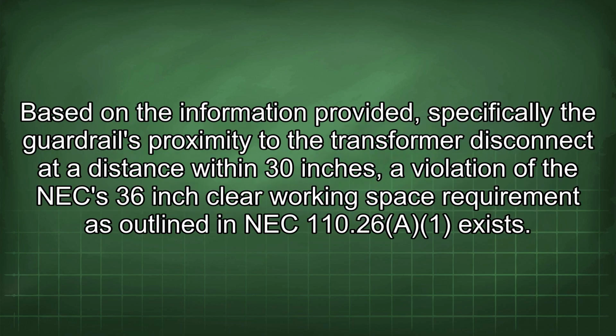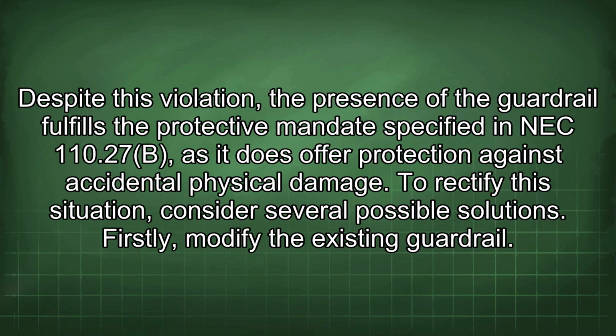Based on the information provided, specifically the guardrail's proximity to the transformer disconnect at a distance within 30 inches, a violation of the NEC 36-inch clear working space requirement as outlined in NEC 110.26(A)(1) exists. Despite this violation, the presence of the guardrail fulfills the protective mandate specified in NEC 110.27(B), as it does offer protection against accidental physical damage. To rectify this situation, consider several possible solutions.